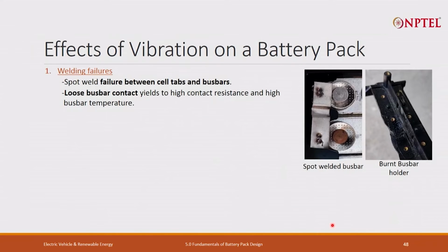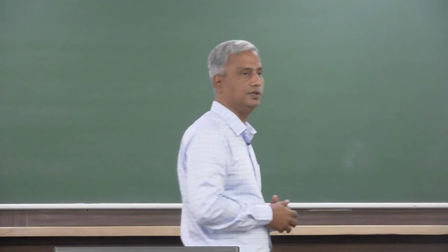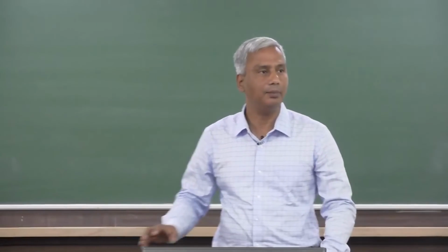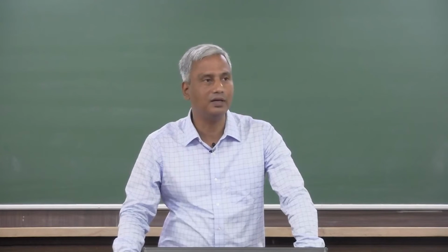What are the effects of vibration on a battery pack? Several things can happen. The first one is welding failures, the spot weld between cell tabs and bus bar, which can be done through laser, resistance welding, or ultrasonic welding. If it breaks, there is a chance of high contact resistance. If I have multiple spot welds and some have failed, I now have more contact resistance, which produces more heat. And if more heat is produced, the part will locally start melting.